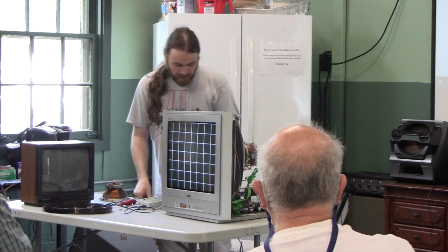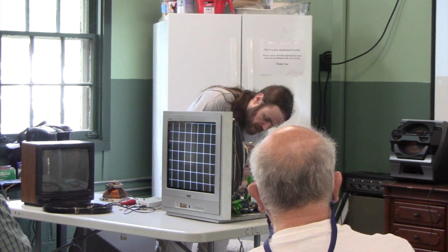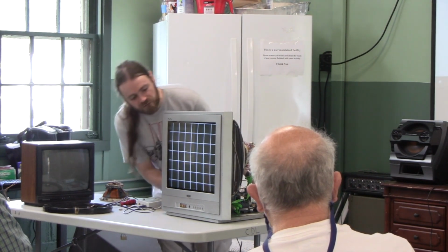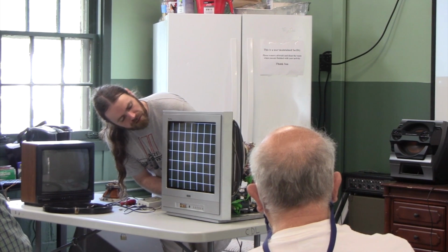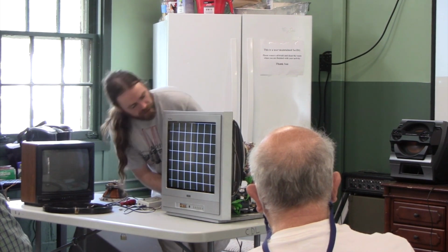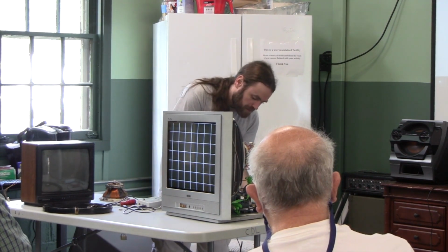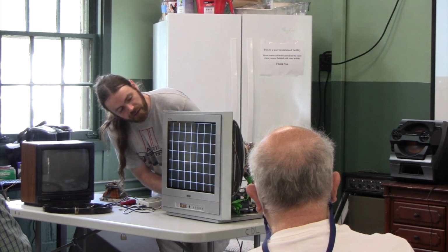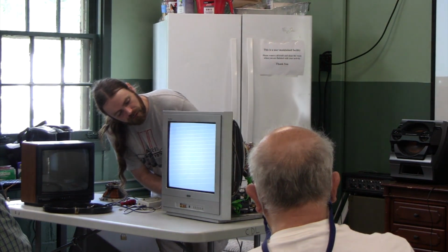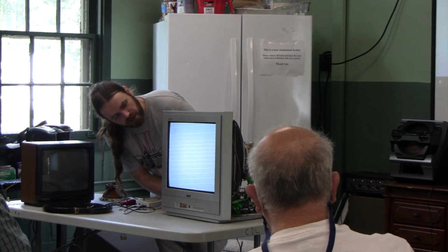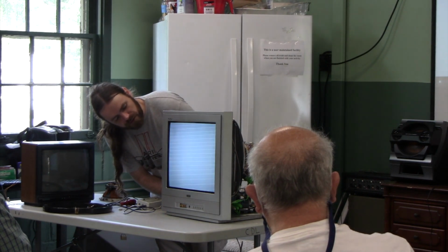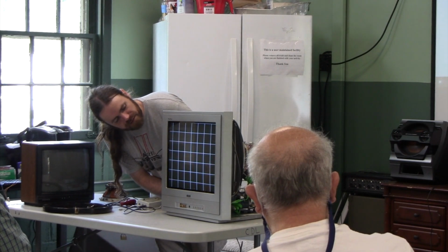And you can compensate for that a little bit by adjusting these controls and changing the focus voltage to dial it in, make it bright, make it sharper, and adjusting the screen control here. So I can make it way too bright. And then you can adjust that so the blacks are actually black.